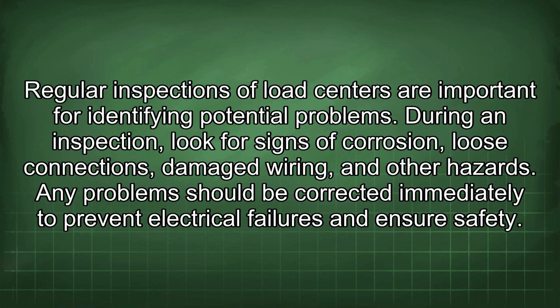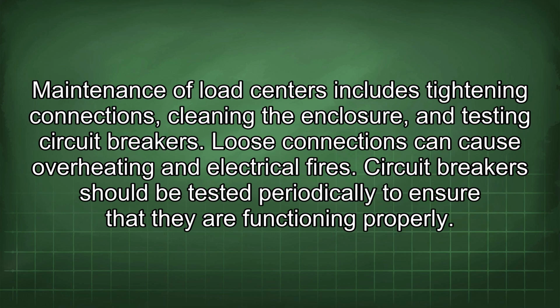Regular inspections of load centers are important for identifying potential problems. During an inspection, look for signs of corrosion, loose connections, damaged wiring, and other hazards. Any problems should be corrected immediately to prevent electrical failures and ensure safety. Maintenance of load centers includes tightening connections, cleaning the enclosure, and testing circuit breakers. Loose connections can cause overheating and electrical fires. Circuit breakers should be tested periodically to ensure that they are functioning properly.